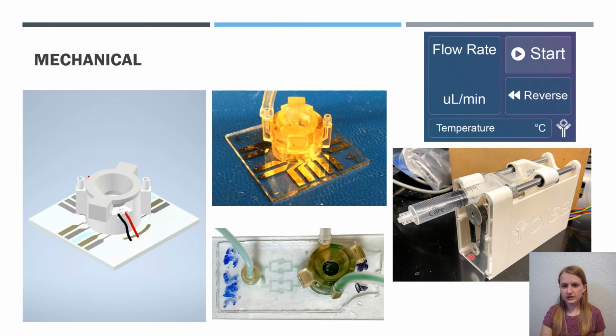So the syringe pump seen on the right here can pump down to 1 microliter per minute. Accuracy is what we aim for. It can actually pump down less than that, but that was the goal. And with this syringe pump, we also made a GUI. Here you can see the front page of the GUI where you can enter a flow rate, start, stop, and reverse the syringe pump, all on a touchscreen that's attached to the syringe pump. It also records the temperature here, so we can vary the temperature of the syringe pump liquid that's in there, because cells usually like a very specific temperature to be happy.